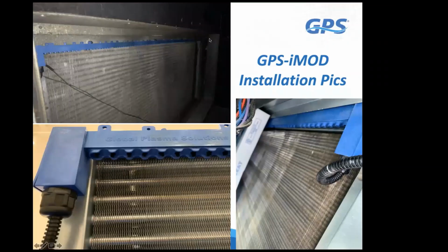Here's some additional examples of the systems. You have rare earth magnets that are provided with these bars, so they just snap the bars right in place. And the other benefit here is ease of installation. It only takes up 1 inch in the direction of airflow, so it doesn't matter that it's a packaged rooftop unit, as you see down here on the right-hand side, or a larger air handler.